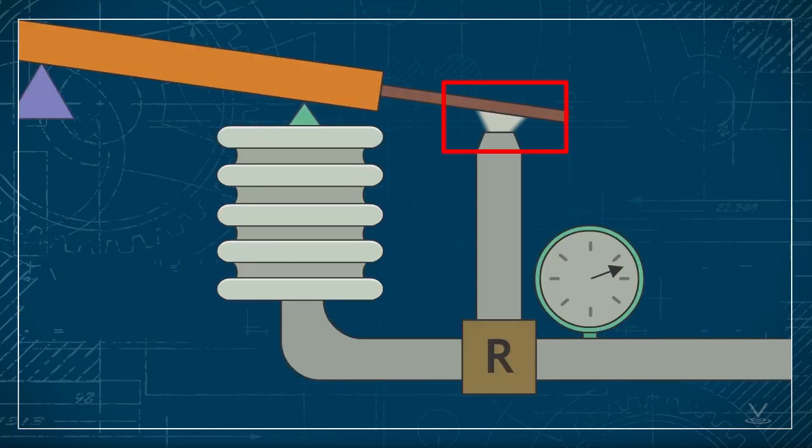This is where the controller computes any difference in the measured signal and setpoint. If the beam's position changes, it changes the relationship between the flapper and the nozzle, which results in changes in back pressure.